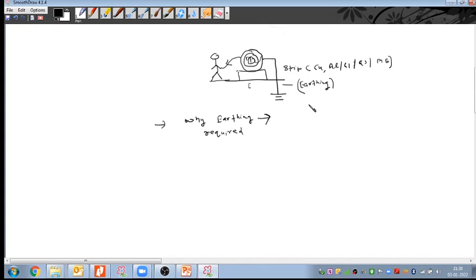Second point, let me take one technical example for the system earthing. This was the equipment earthing. I will come to the types of earthing just after this discussion. Here I have the main bus bar, then a circuit breaker, and thereafter one transformer, that is delta here, and let me take star winding on the LV side, and here we have the LV side bus. Suppose I have not done this neutral point to earth. If the neutral, N, is not earthed, then what will be the effect on the system?